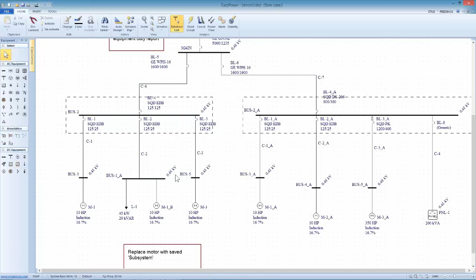The same type of error checking applies when I'm looking at panels and motor control centers. Again, I want to make sure I'm completing each of these stages, and part of that is making sure we have the right configuration as far as how our system wiring is set up. Part of the incoming tab is to describe what type of protective device I have on this particular panel. If I have a breaker, then I control the description of that breaker with incoming device settings. This is handled just like any other low voltage circuit breaker in the library, and I want to fill out the same amount of information. Here I've described a generic part number.